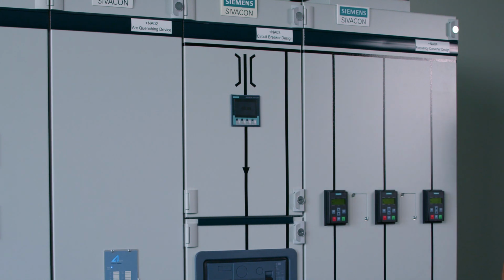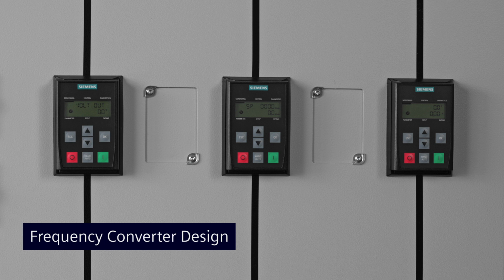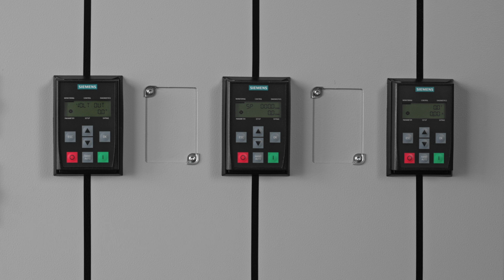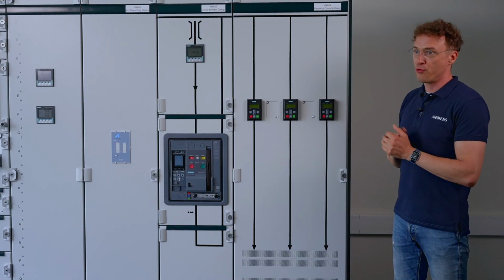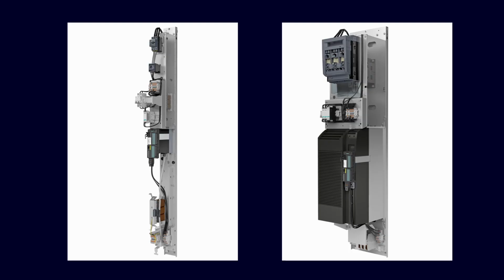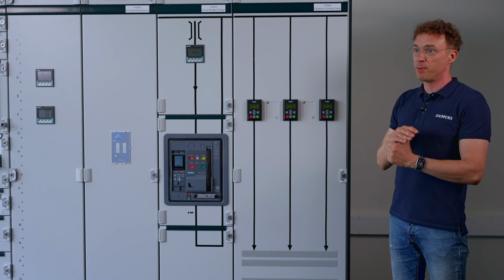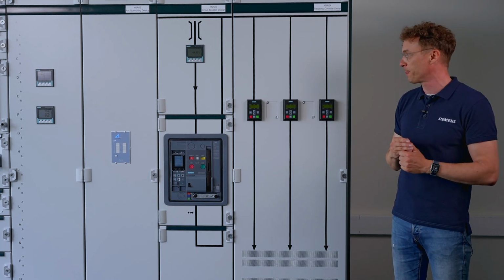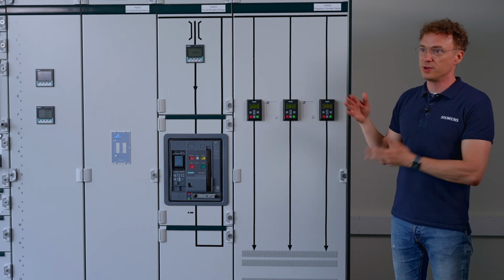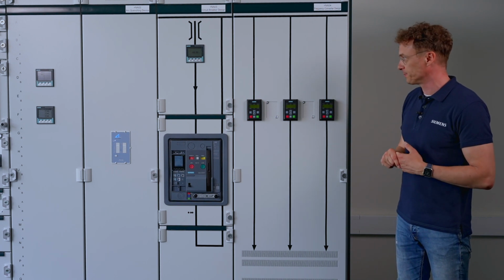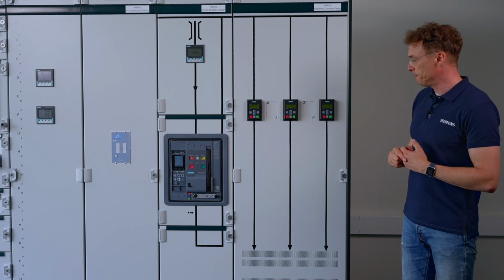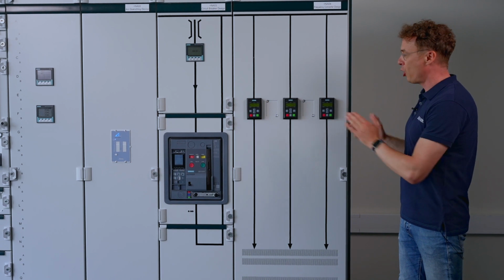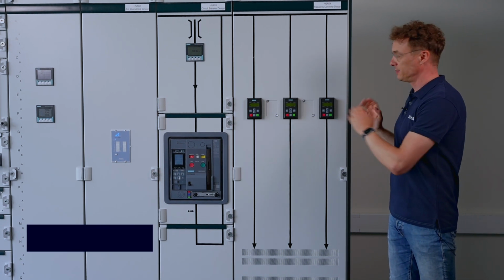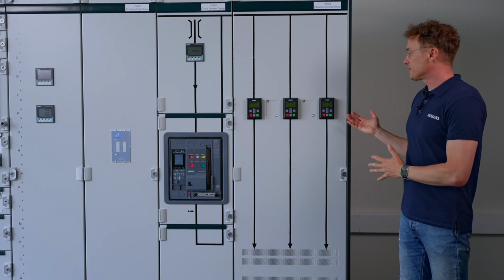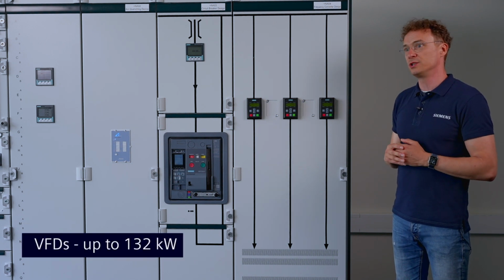On the right-hand side, we have our frequency converter design. This is a type of fixed-mounted installation. It consists of modules for the feeders, and on each module, all the components that belong to one feeder are installed. So, for instance, the power module of the SINAMICS G120 series, line reactor, choke, and everything that belongs or is available for one feeder. It's a very compact design. Depending on the rating of the feeders, up to 9 modules can be installed in one section, and the modules themselves have a rating of up to 132 kilowatts.